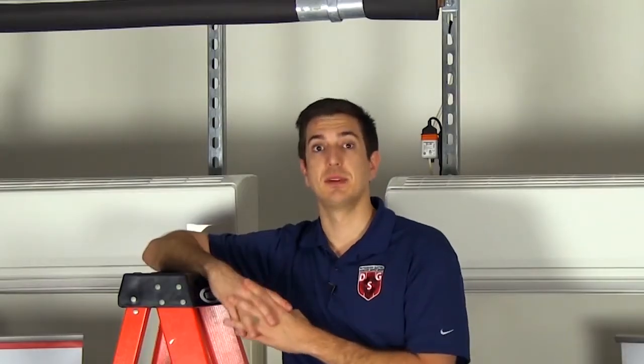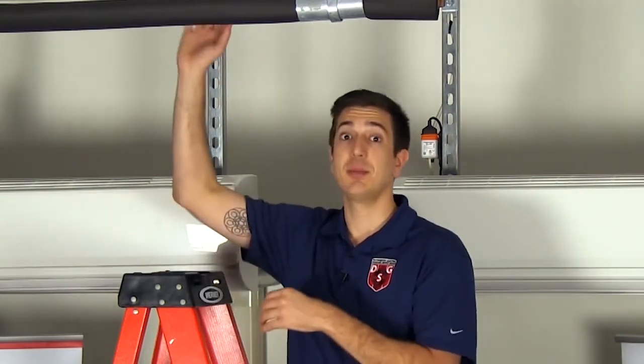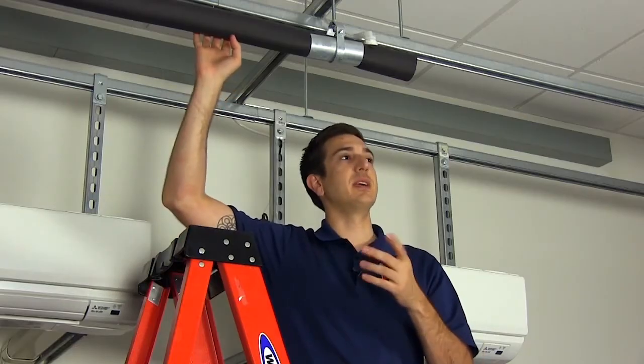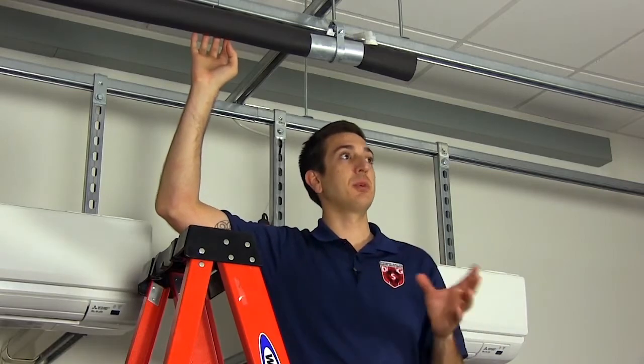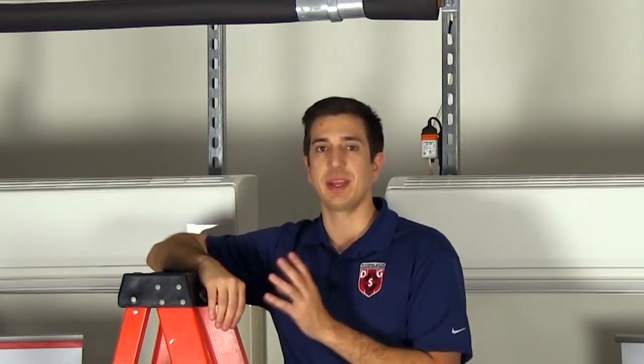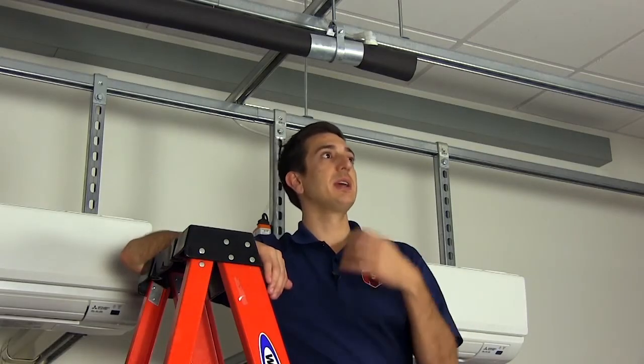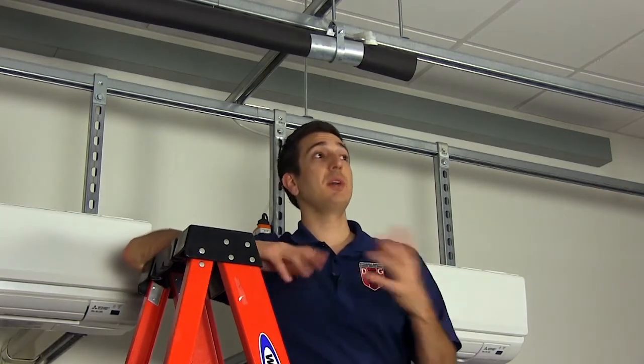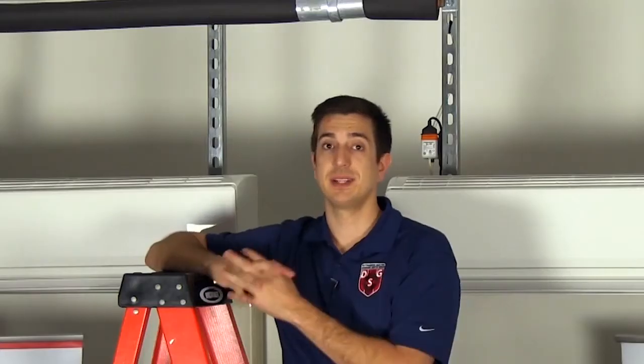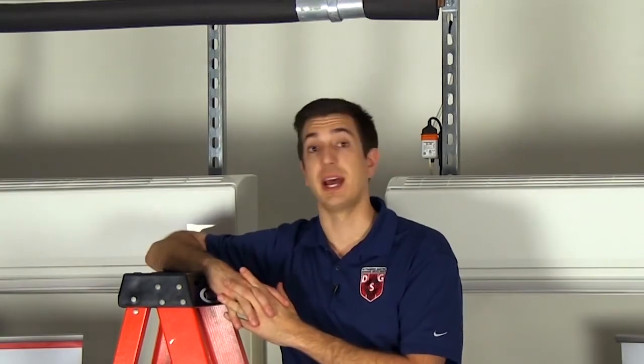In this example of the PA error code, we're using a system that's utilizing a common drain. The common drain is there for multiple indoor and outdoor units. So what would happen if a clog occurs at the end of this drain line? Say the units all the way at the beginning of the drain continue to run, but water starts to back up into the very last air handler. Water then fills the pan, kicks the float switch, even though the unit's not calling for cool. Well, that's exactly how a PA error code can happen.